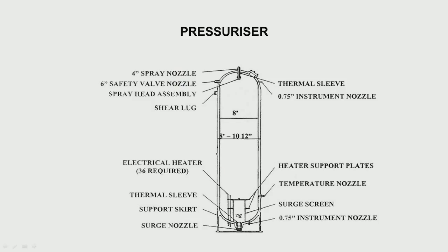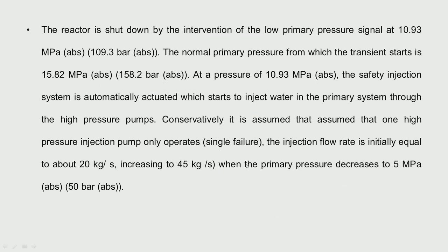This gives a clearer picture of the pressurizer. You see the electrical heaters — quite a good number, about 36, maybe a megawatt of power. Then you have the spray nozzle, a nozzle for the safety valve, and instrumentation nozzles which measure temperatures. The size of this pressurizer is about 8 feet.